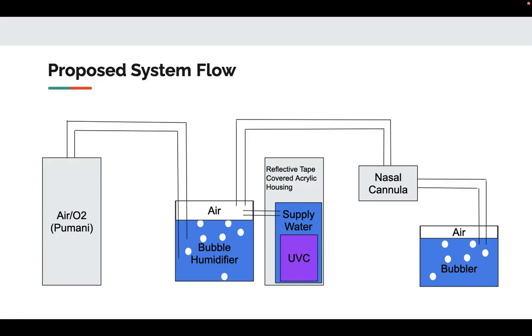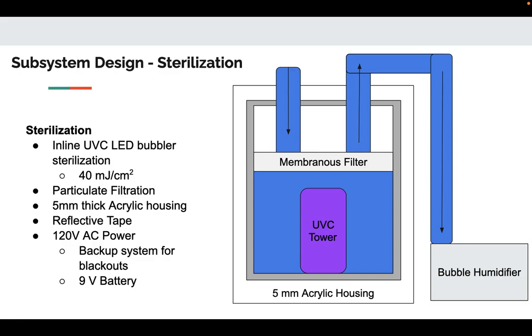The bubble CPAP is also unique in that whenever pressure is changing in the system between the infants inhaling and exhaling, bubbles can be released at the end of the system, and this can help regulate pressure and help allow the infants to exercise breathing a little bit more, and this has been shown to help infants get off of CPAP machines quicker. So, our subsystem design, going into the sterilization. This will be an inline UVC LED sterilizing system. So it will need an energy requirement of 40 millijoules per centimeter squared. And so this is the capability of each of the UVC LEDs.